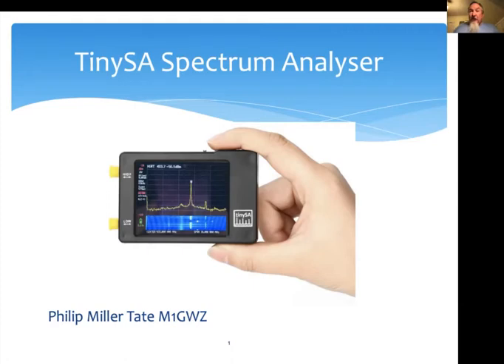Of course, like everything else, there's a compromise. There has to be a downside, and the downside of the fast Fourier transform digital process is that it always, and I emphasize this, it always introduces artifacts or spurious signals, sometimes shortened to spurs, in the output. There's no way around it, unfortunately. There are ways of mitigating it, there are ways of reducing it, but you will always get some artifacts in the output that are not real. And I emphasize that now because a lot of what the TinySA and other digital spectrum analyzers are about has to do with reducing, or noting and taking steps to reduce, those artifacts. That's very, very important.